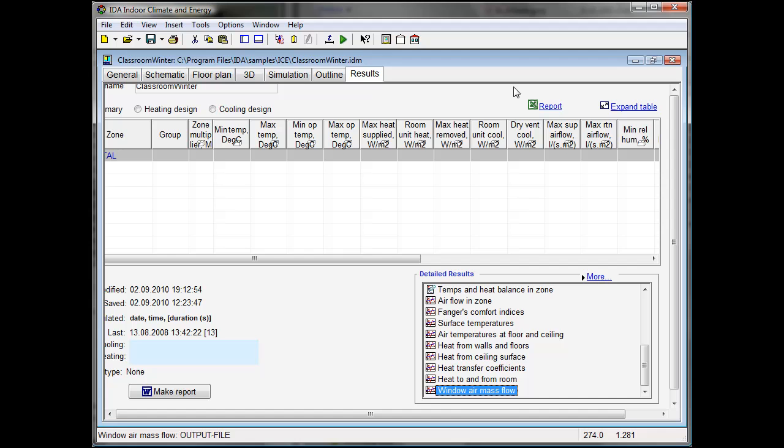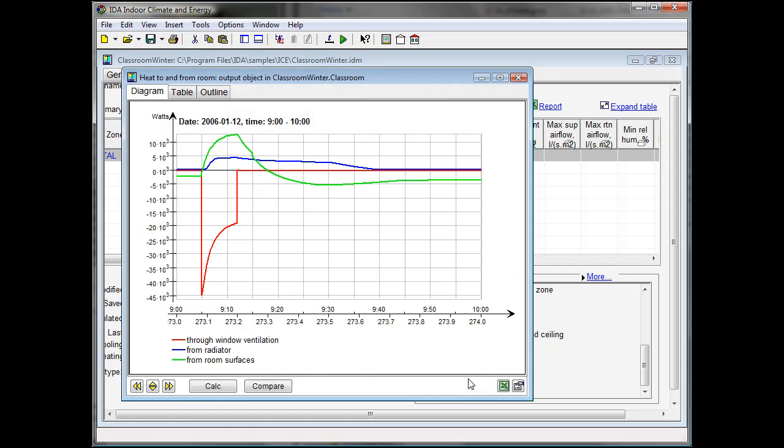The question was now what size of radiator is needed to compensate this heat loss through the windows. We can see here heat loss to and from the classroom during the same break. In red we can see the heat loss through the window which goes up to 45 kW at the beginning of the break and 20 kW at the moment where the windows are closed.